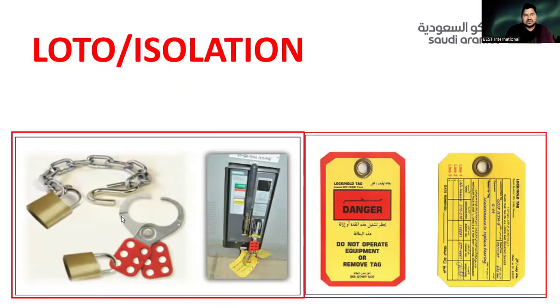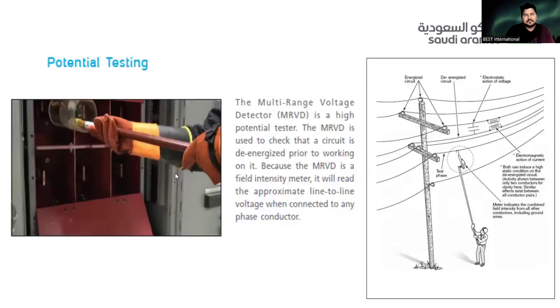This is just an example of LOTO in isolation, how devices look, how the tag looks. This is just an example in the picture. Then you put a lock. There is potential testing available, like a multi-range voltage detector, which is a high potential tester, you know. But imagine if your company does not have it and you got trained. Bear in mind the knowledge, the information, will not be valuable until you implement it. If there is a multi-range voltage detector, make sure your company has it. If they don't, as an electrical engineer, electrician, electrical safety manager, or electrical department manager, please raise a requisition that you need a multi-range voltage detector.